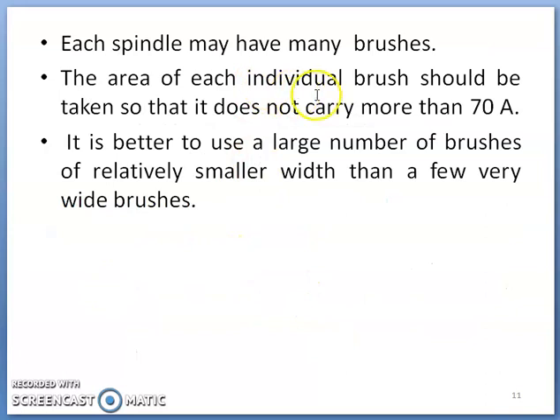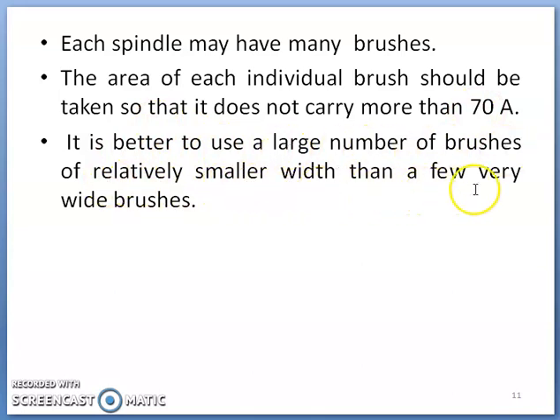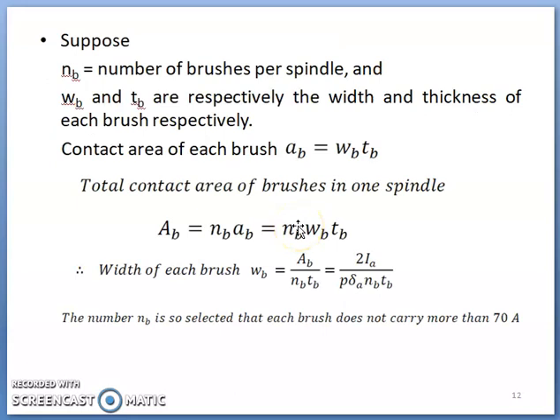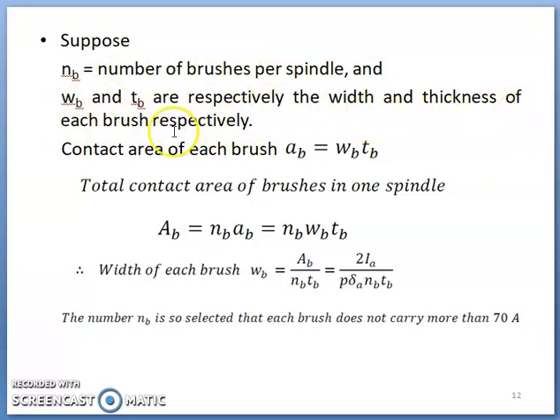The area of each individual brush should not carry more than 70 amps. It is better to use a large number of brushes of relatively smaller width than a few very wide brushes. The number of brushes may be increased depending on requirements.